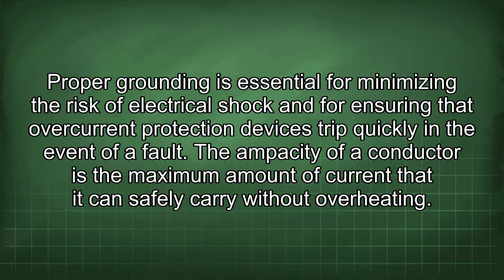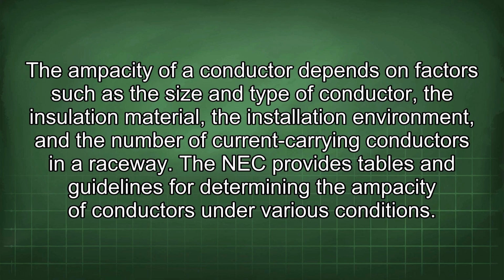The ampacity of a conductor is the maximum amount of current that it can safely carry without overheating. The ampacity of a conductor depends on factors such as the size and type of conductor, the insulation material, the installation environment, and the number of current-carrying conductors in a raceway. The NEC provides tables and guidelines for determining the ampacity of conductors under various conditions.